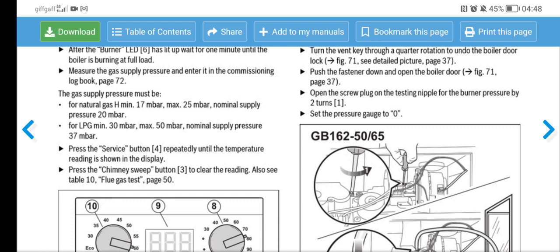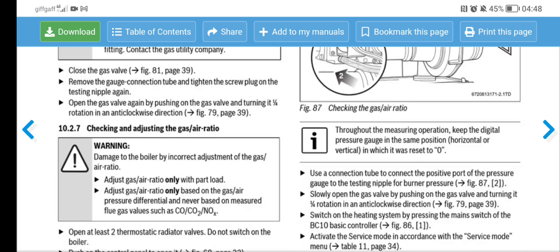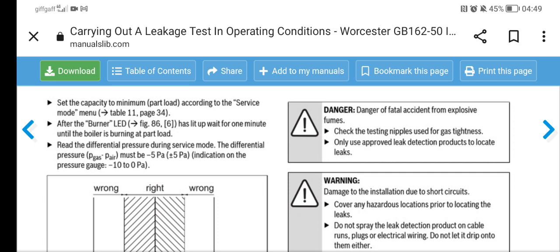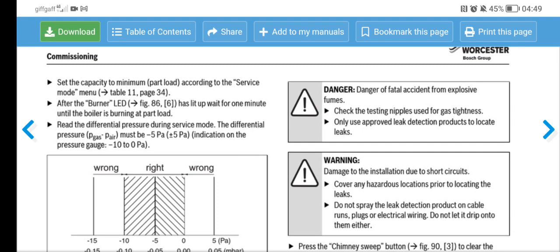Now it says open the screw plug on the test nipple for the burner pressure by two turns. Set the pressure gauge to zero, so zero your gauge. Use a connection tube to connect the positive port of the pressure gauge to the test nipple for burner pressure. It says set the capacity to minimum, that is part load, according to the service mode. After the burner has lit up, wait for one minute until the boiler is burning at part load. Read the differential pressure during service mode. The differential pressure must be minus five Pa indication on pressure gauge, minus 10 to naught Pa.